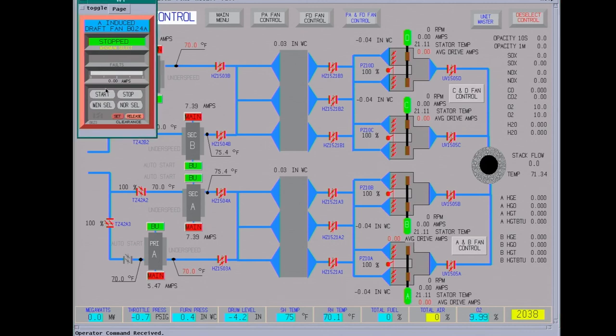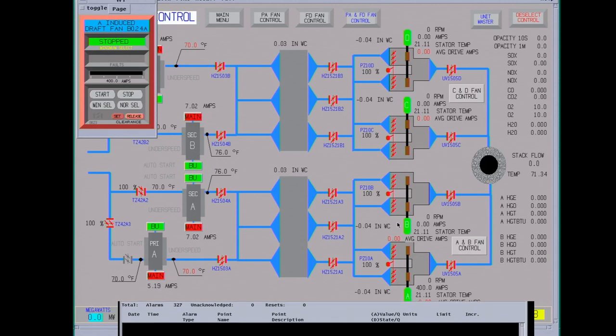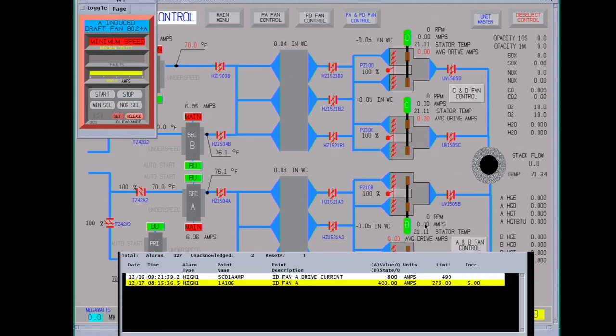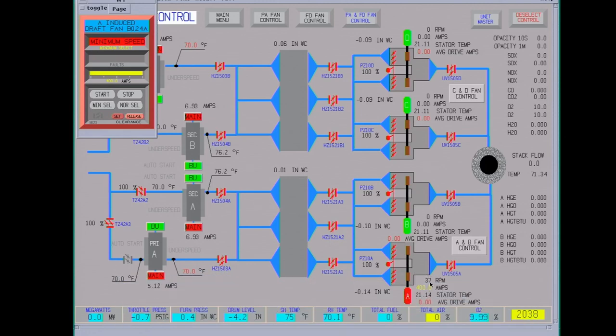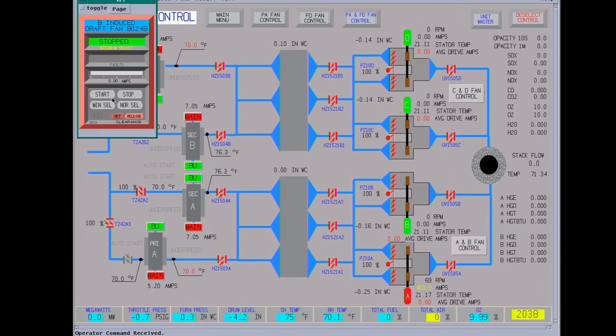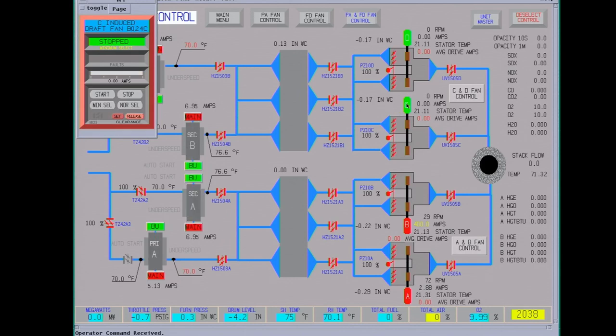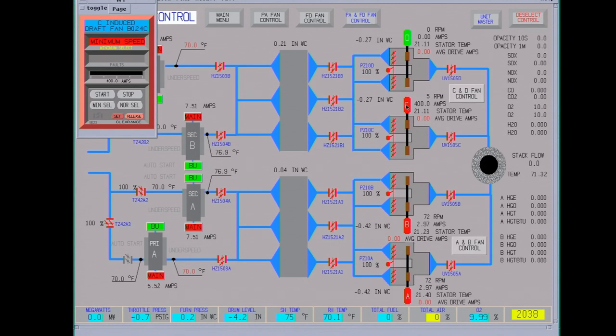Okay, we're going to start in what's called minimum select. This is slow speed, about 60 RPM. It's kind of like a turning gear. You'll roll the fans. Usually want to run it for about four hours just to make sure that there's no warpage in the shaft. So it's coming up to speed. I say the boiler is full, it holds about 120,000 gallons of water. It takes a couple hours to fill it, plus you need warm water, deoxygenated water going into the boiler.